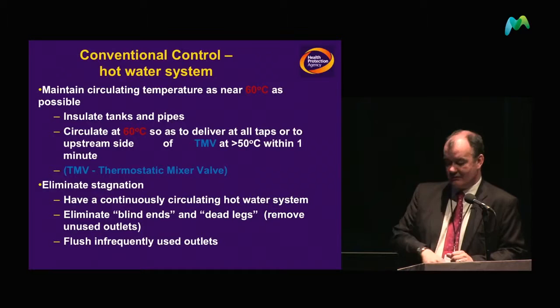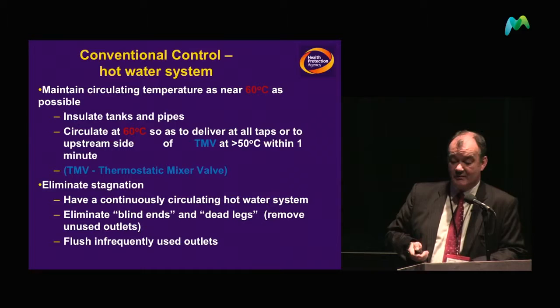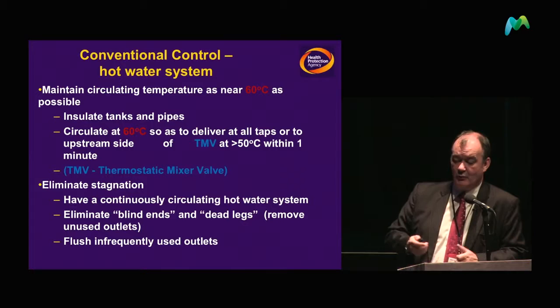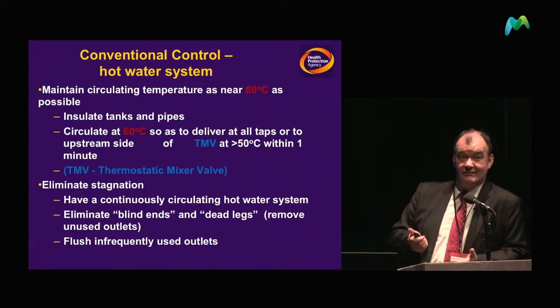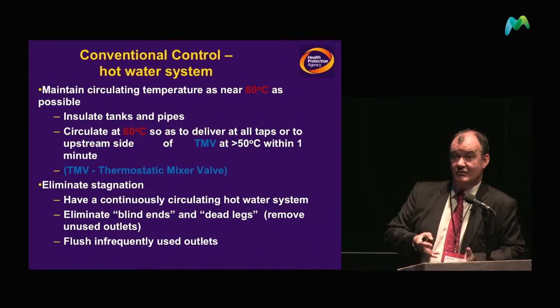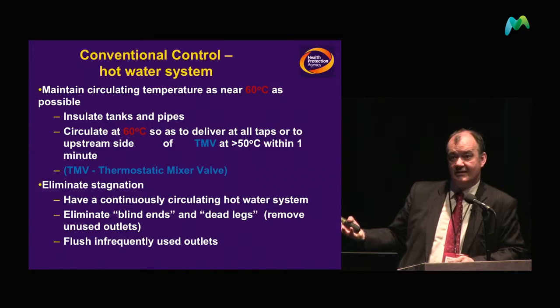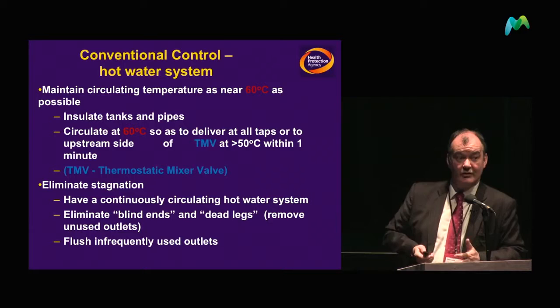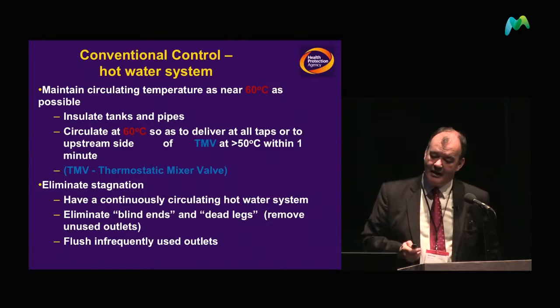The key element in maintaining a conventional hot water system is trying to keep it as near to 60 degrees as possible. However, one of the big problems is thermostatic mixer valves — TMVs — which were introduced to prevent scalding and deliver water at about 40 to 42 degrees at the point of use. They do produce their own problems: while we reduce the risk of scalding, we increase the likelihood of Legionella growing — the classic trading off of one risk against another.